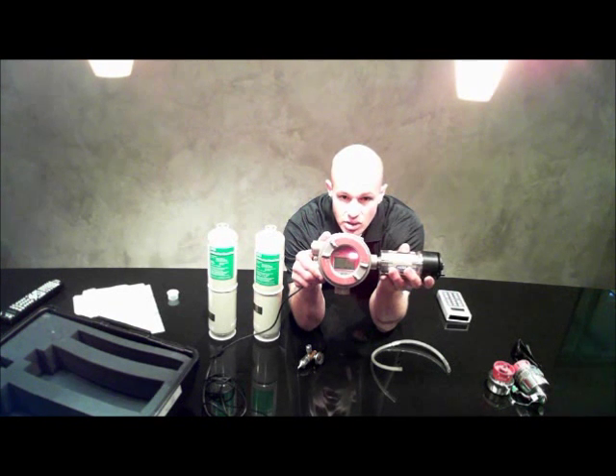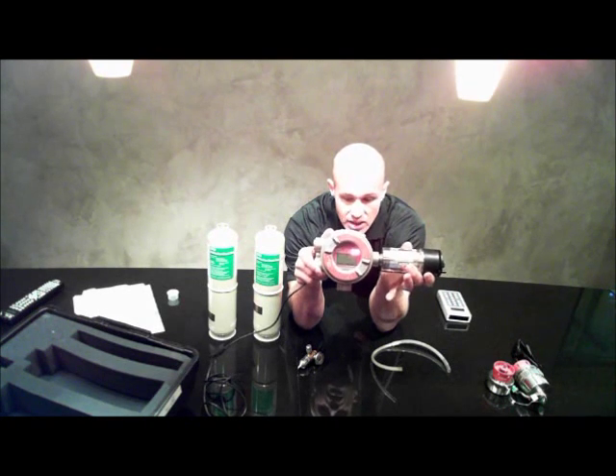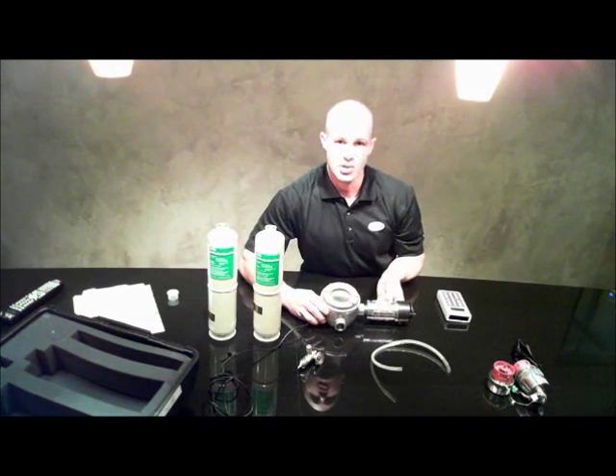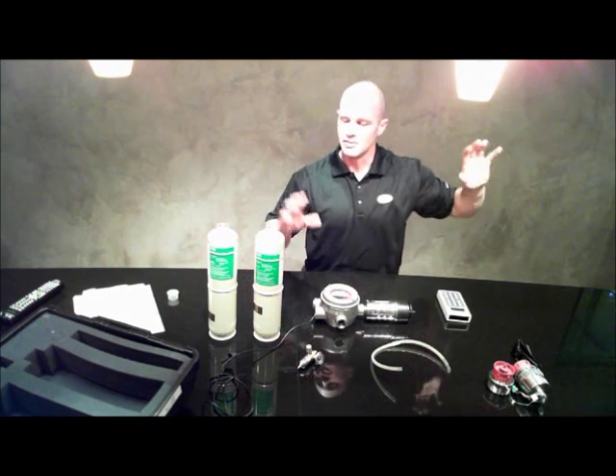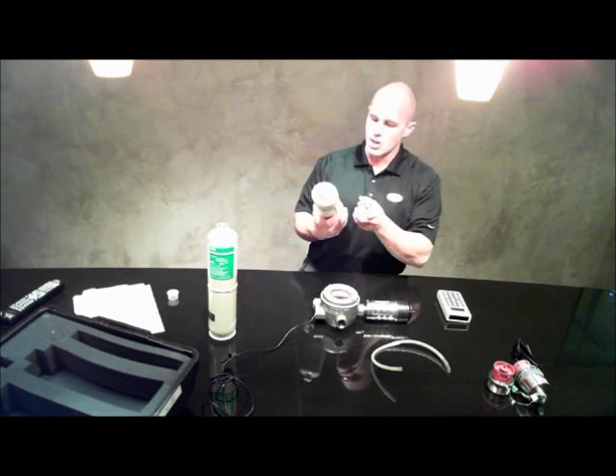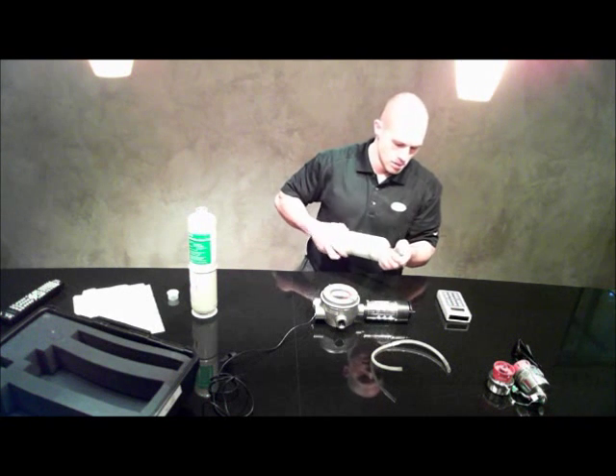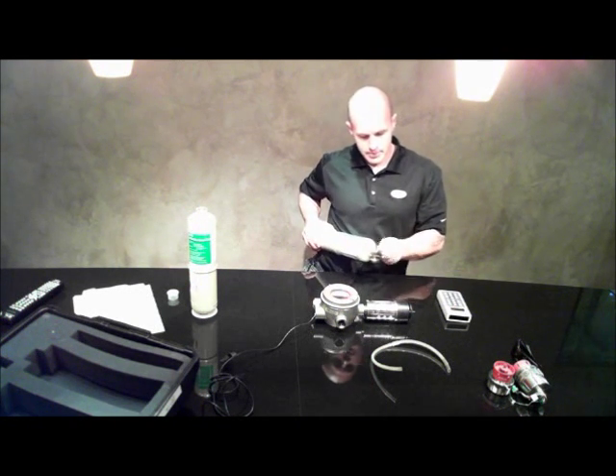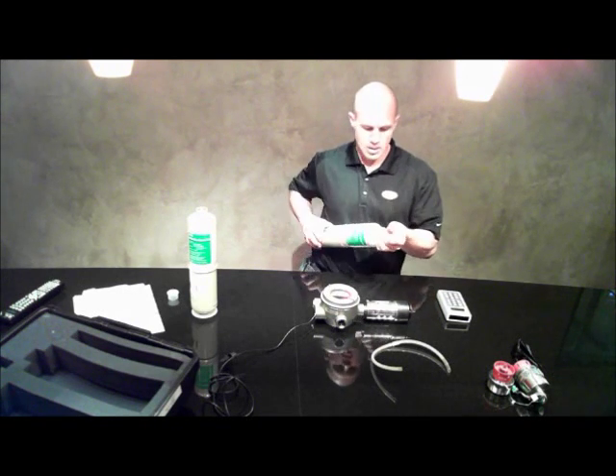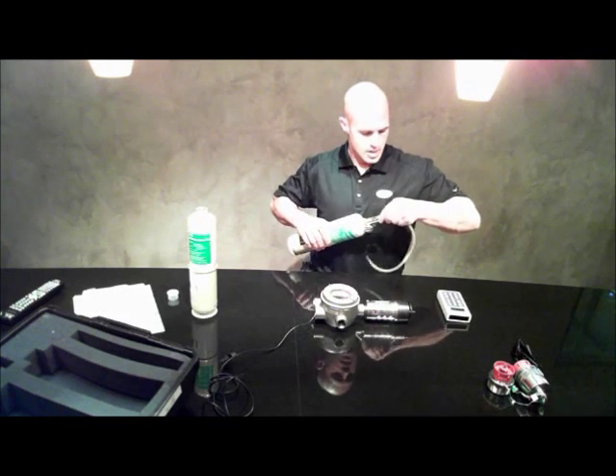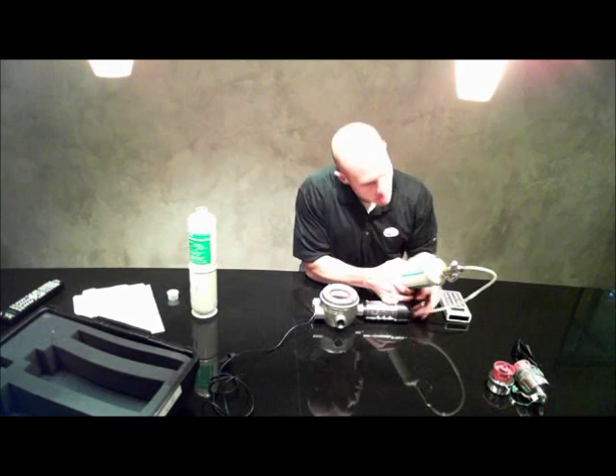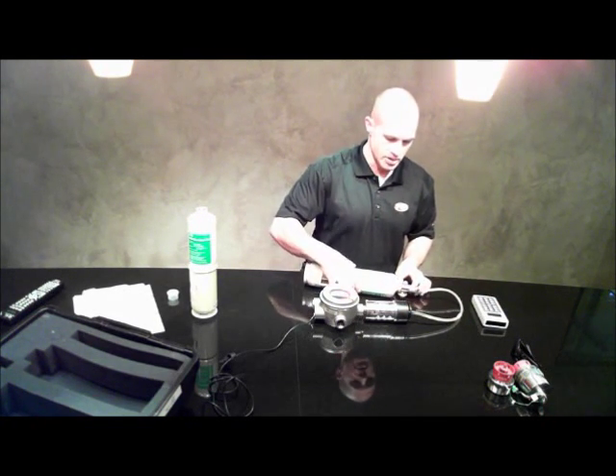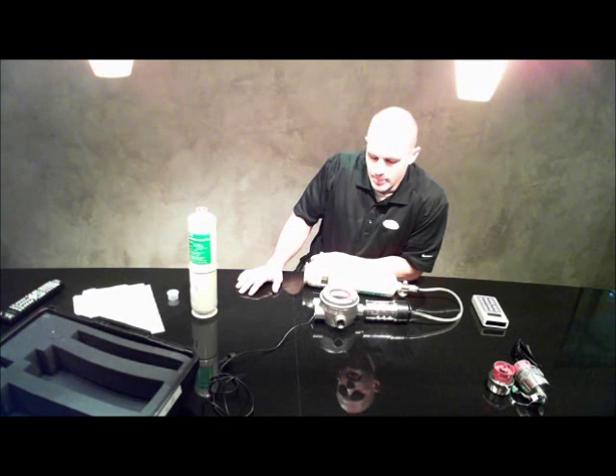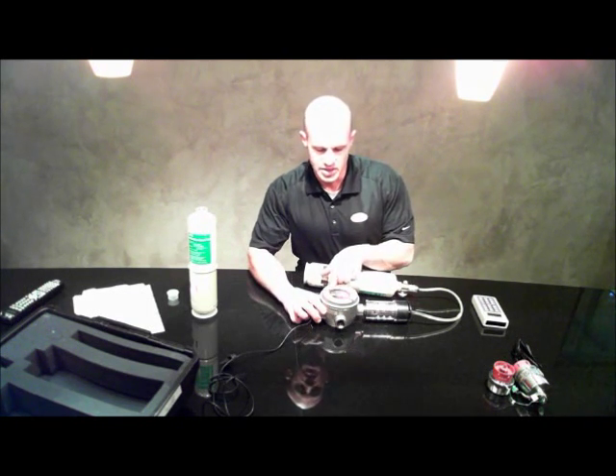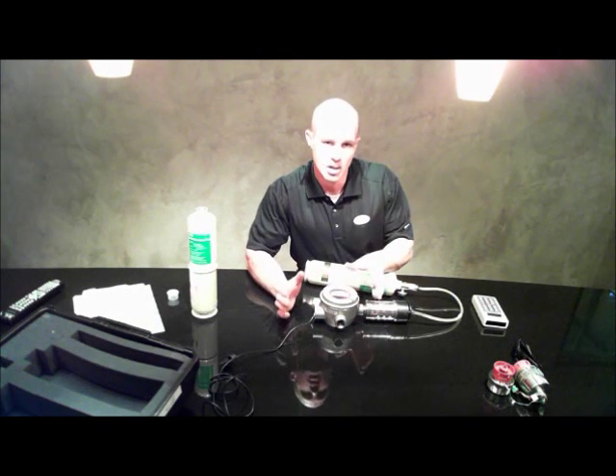This will give you 30 seconds to get your gas hooked up and get it flowing. The gas does not need to flow during the 30 seconds unless you've got a sensor that's remote mounted a considerable distance away, 50 feet, 100 feet. You need that gas to be pushing through. So you're going to do your zero gas first. Oh, somebody had that cranked open. So, zero gas. Just let that flow. Usually takes about 30 seconds, 45 seconds, somewhere in between there. And on the display, it says apply zero gas. So it does give you a visual indication of what you need to be doing at the time.